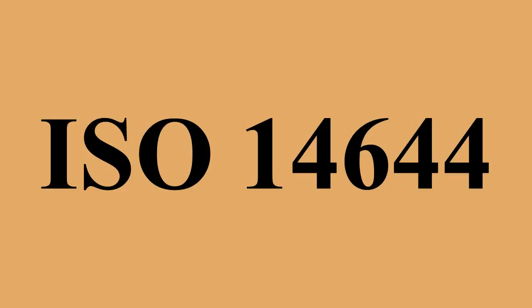Part 5 — Operations — provides the basic requirements for operating and maintaining clean rooms and associated controlled environments. This standard addresses requirements basic to the operation of all clean rooms regardless of application. Topics include operational systems that must be in place, selection and use of appropriate clean room garments, training and monitoring of personnel and activities, installation and use of equipment, requirements for materials used in the clean room, and maintaining the clean room environment in a clean, usable condition conforming to design standards. This part was published as an international standard in 2004 and adopted as ANSI/IEST ISO 14644-5-2004 in the United States.